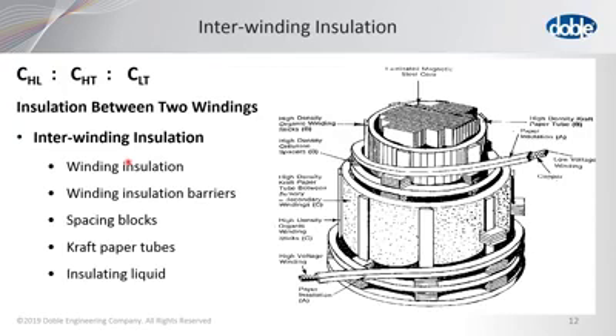So if there is any leakage in the transformer tank at the top, can we perform power factor testing, or is it not recommended until the problem is fixed? My question would be, when you say leakage at the top, do you mean a nitrogen blanket leak? I think that is what he's probably saying, so I'm going to answer the question that way. A leak in the transformer that allows oil or nitrogen out during its lifetime will also allow moisture to go into the transformer. Now, the power factor test is a great way to identify if that may have happened, right? Because moisture will make the power factor go higher.